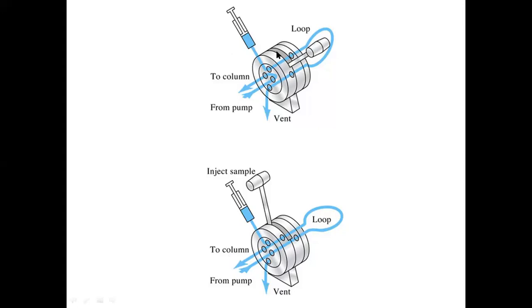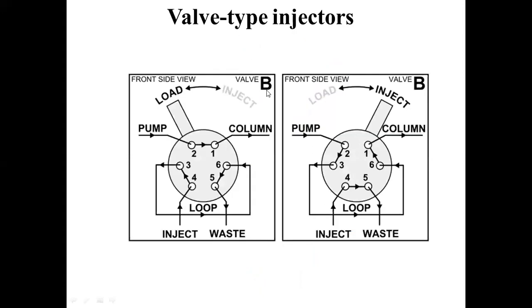So when you load the sample, if you have not brought the loop towards the injection mode, whatever the sample introduced, that will be going as waste. You can see by means of this arrow mark. So once the sample is injected, loaded, you have to bring this rotor valve towards the injection mode. Then the introduced sample is going to join the mobile phase front, then it will be moving towards the chromatographic column. So this is how the rotor valve or valve loop injector will be functioning.